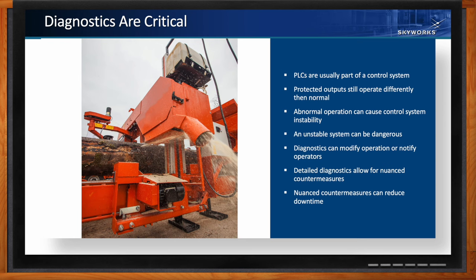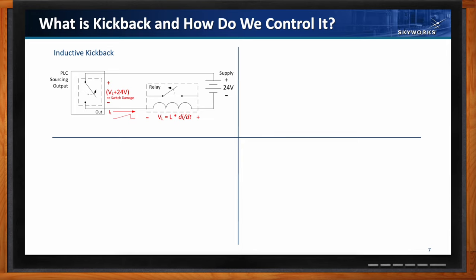Moving on to inductive kickback protection. Inductive kickback is the voltage spike you get when you interrupt the flow of current through an inductor — it's proportional to the current's rate of change and its polarity is opposite the supply. Depending on how fast the current changes, you can end up with a massive voltage across the switch in the output channel, and massive voltage tends to break things when you don't design for it.